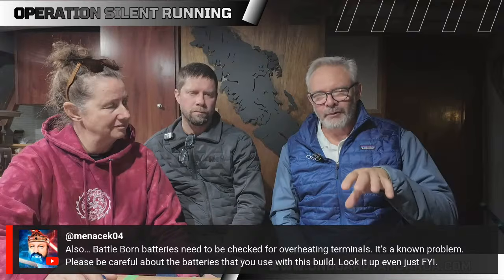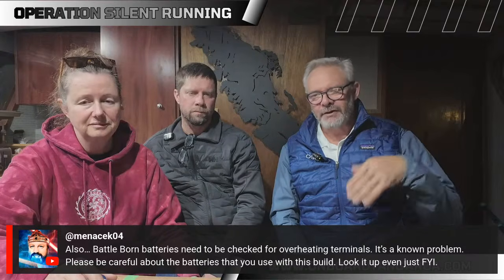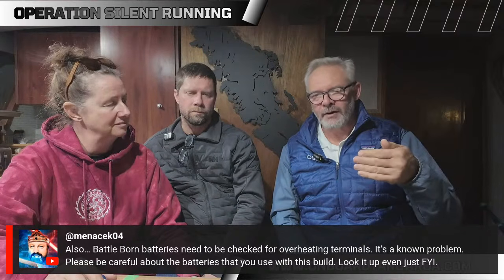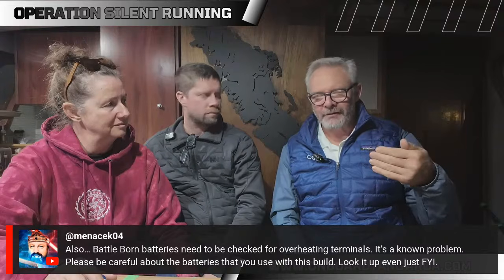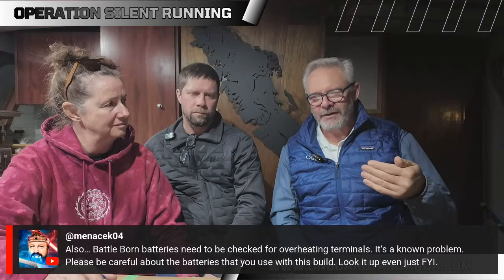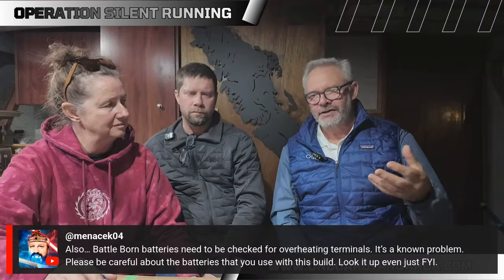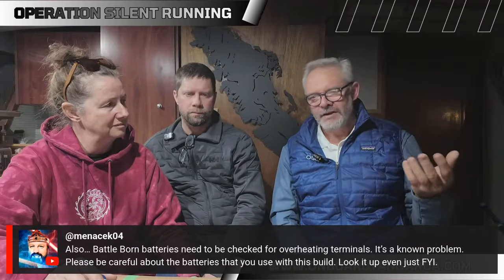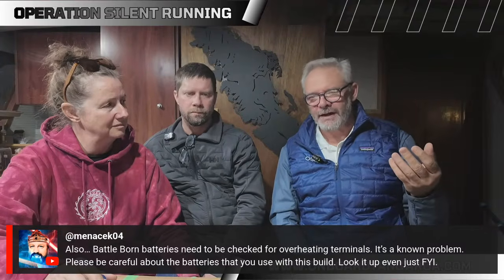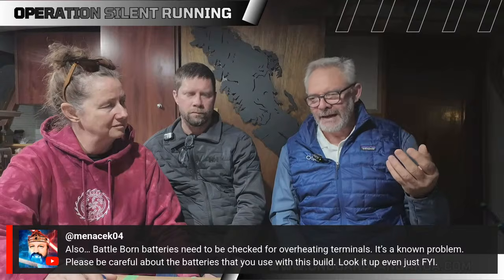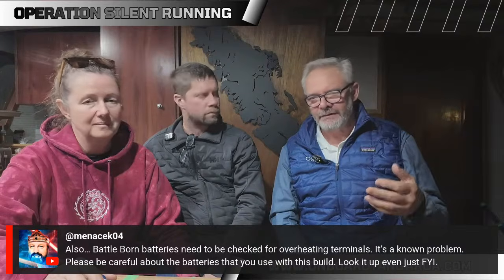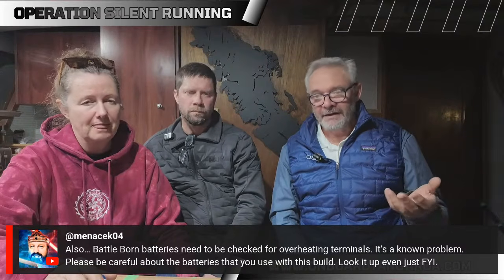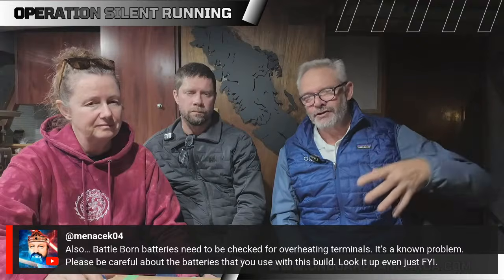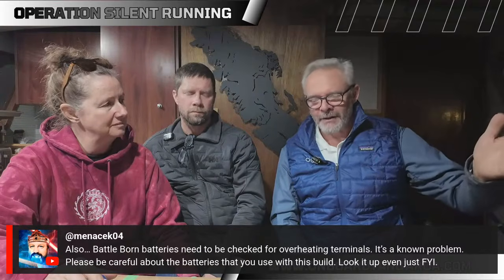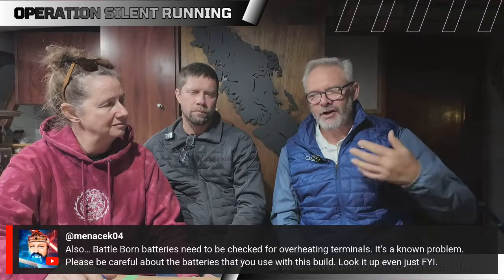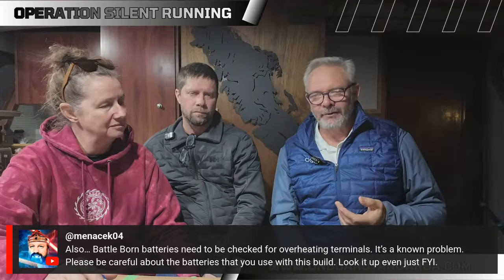Then we get to the battery we're putting in this boat, which is between 1 and 1.5 C, meaning you can charge and discharge it in 1 hour or about 45 minutes. Those are what we call power batteries, designed for managing short bursts—you may have a 5C discharge for a few seconds to start a compressor, or have to run at 3C continuously for some machinery to get up and running. It's designed to manage those huge surges, that dynamic range, while taking the charge without aging the battery from a cycle life point of view.